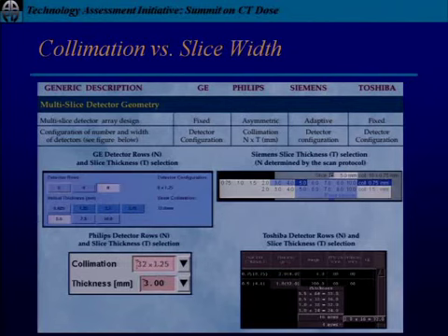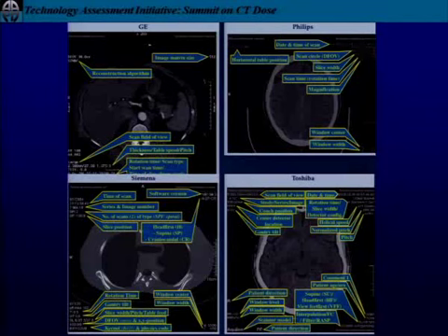The collimation versus image width here, again, different setups, and this was a big challenge early on in the ACR program, which was developed and ready to go live right when multi-slice hit. And so a 5 millimeter, that was an actual 5 millimeter beam and a 5 millimeter image, caused a lot of problems when we went to these N times T, how many cells of how many width, and not all the manufacturers displayed that data. So this is on there.